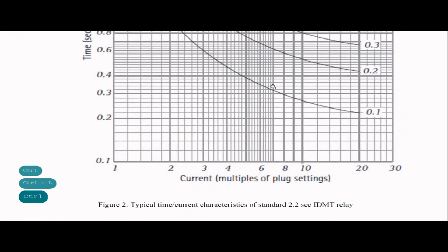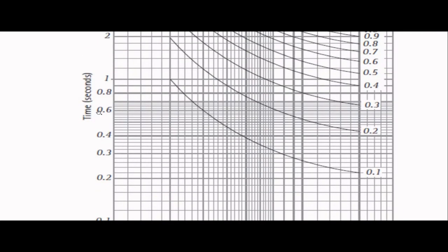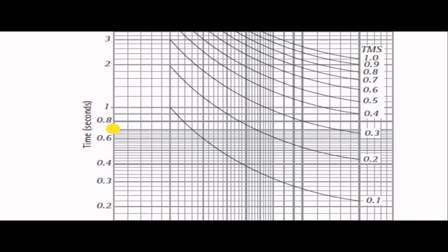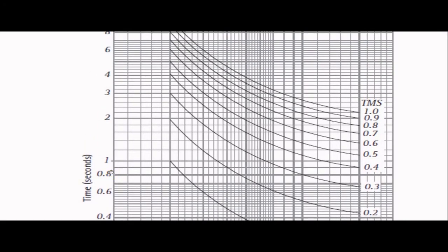This is called the IDMT curve of the electromechanical relay. Now this axis is called the plug setting multiplier, and this axis is the relay operating time in seconds. Now what is called the relay operating time? Relay operating time means the instant between the relay sensing the fault and the relay generating the trip signal.